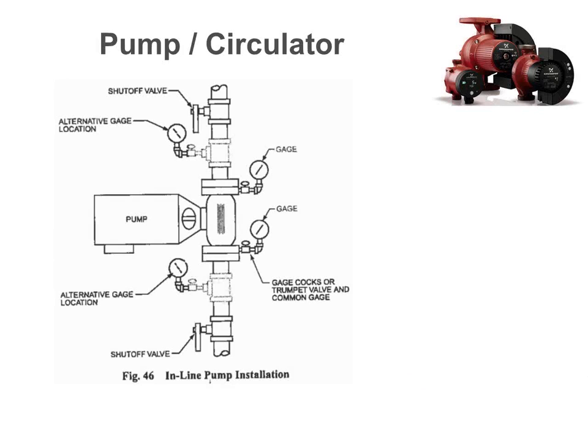Gauges are a good thing, especially if you're doing larger circulators. But the biggest thing is don't put a bunch of gauges on there. You're actually better off to have the gauge itself with the shutoff valve, or the gauge cock, as it's called, right there. Brian's pointing out, have those on there. If you have one gauge and then a second gauge, one might be a little bit out of calibration versus the other, and you don't know that.